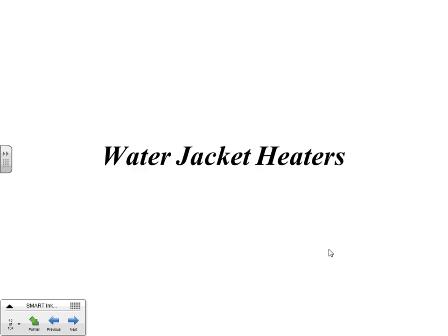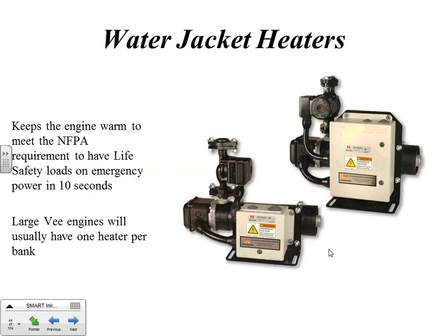Water jacket heaters. There's a code in the NFPA for legally required engine generator sets. It says that thing has to be started and transferred online in 10 seconds. So that's a pretty hefty requirement. So even in summertime, you're going to see, especially diesels, will have water jacket heaters plugged in all the time because they've got to come on in 10 seconds by code.